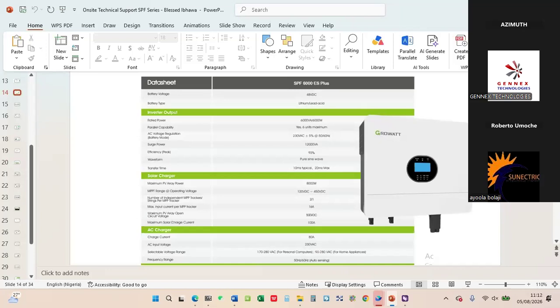And the last question you mentioned, for battery configuration with lithium, it depends on the kind. For example, if your client is using AGM, go to program 5 of the inverter, you'll see AGM, just select it. If it's flooded, just select it. Where the problem is now is lithium - when it's lithium, we have different protocols. If it's Growatt, it's either 51 or 01, depends, so just try 01, if it doesn't work, try 51, depends on the battery. We're going to share a battery compatibility list you can check. For some other batteries like Pylontech, it's 52 - different numbers like that. So when you install your machine, it's very important to set the right protocol so the machine can charge very well. Any issues? I hope that answers the question.